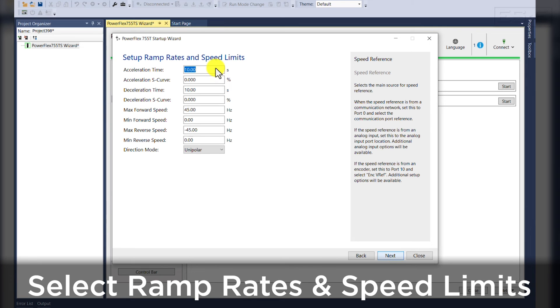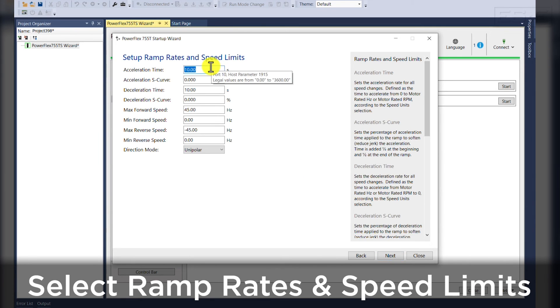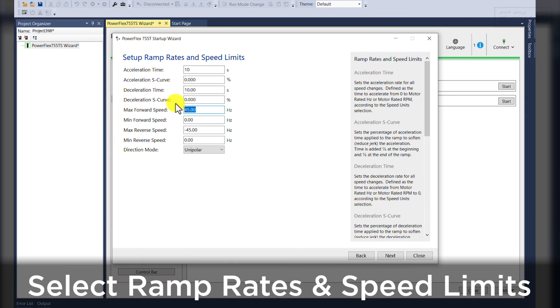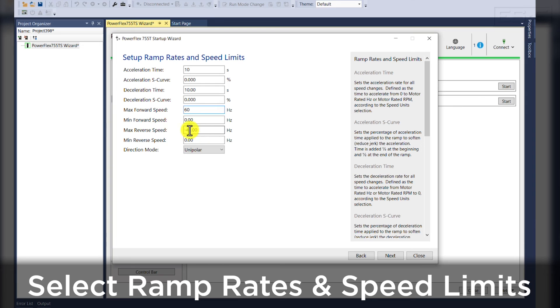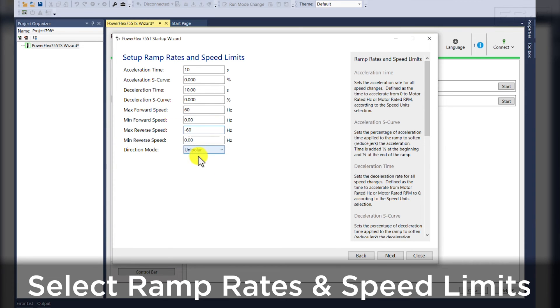Our ramp rates and speed limits. We'll want to use a 10 second acceleration and deceleration, max forward speed 60 hertz, maximum reverse speed negative 60 hertz, and a unipolar direction mode.